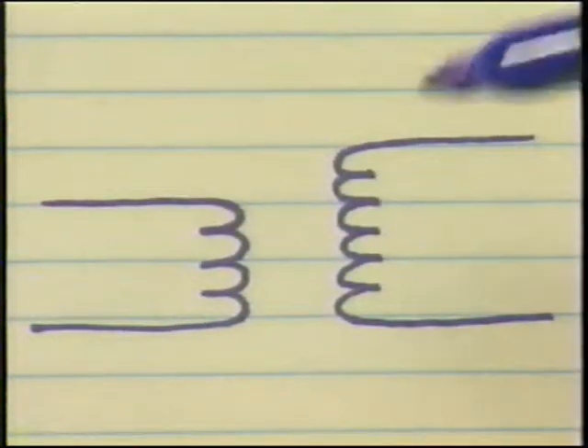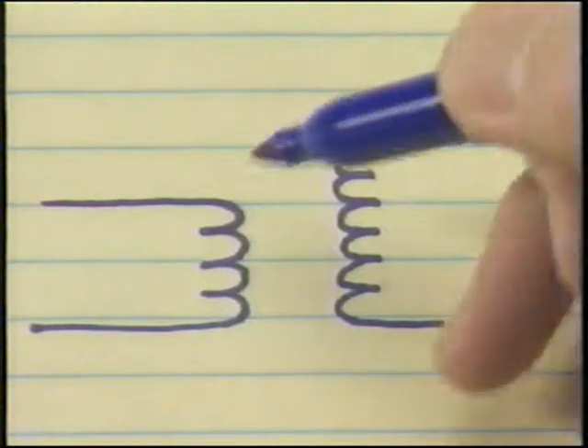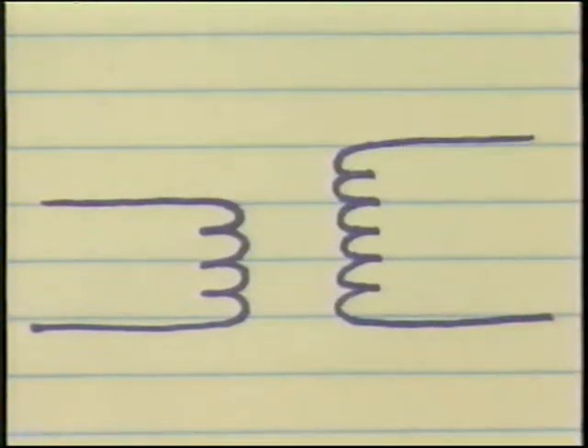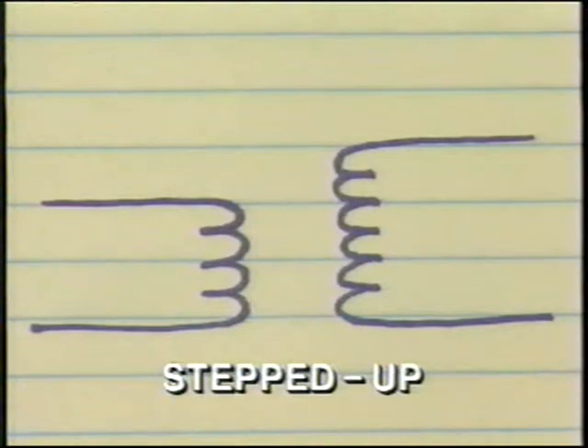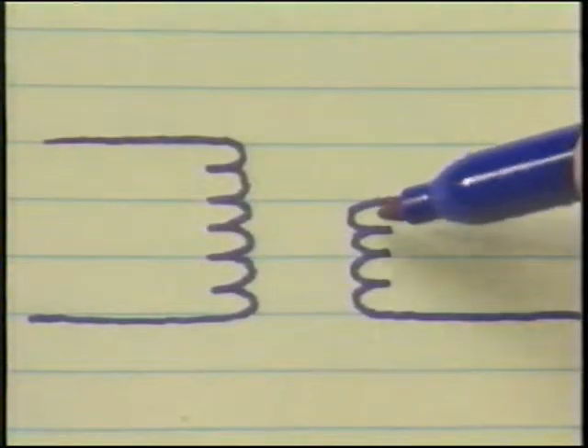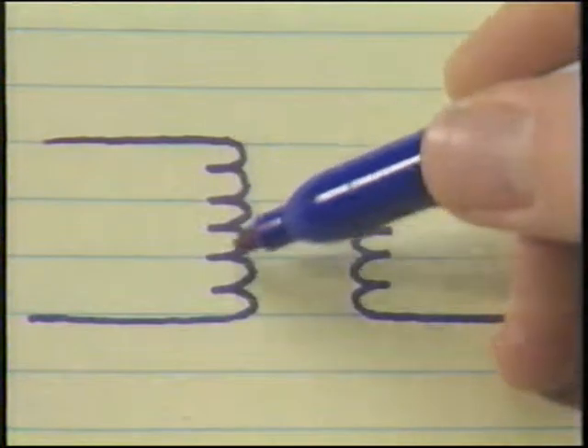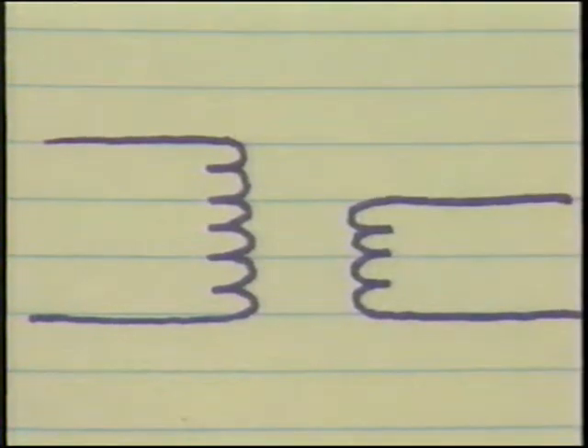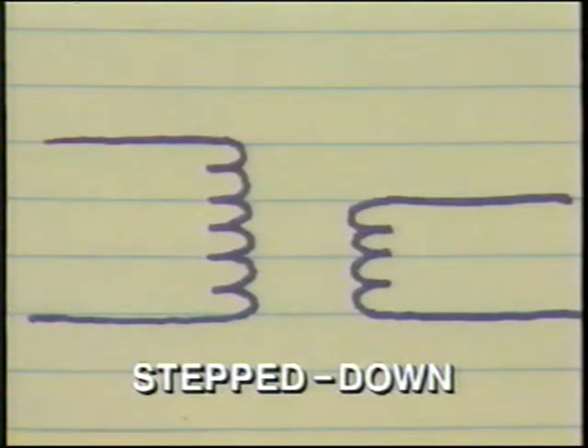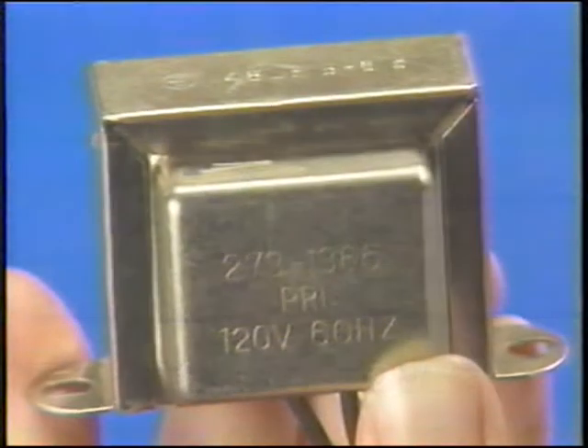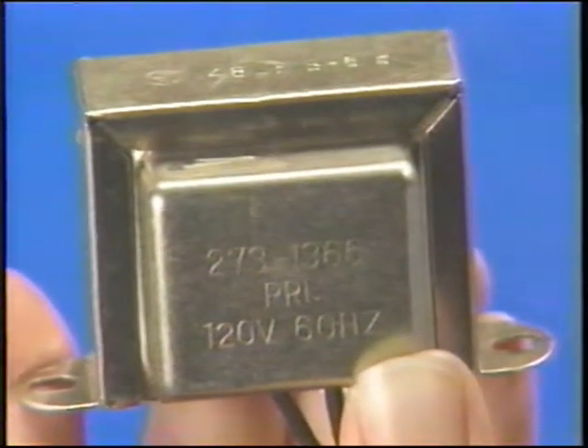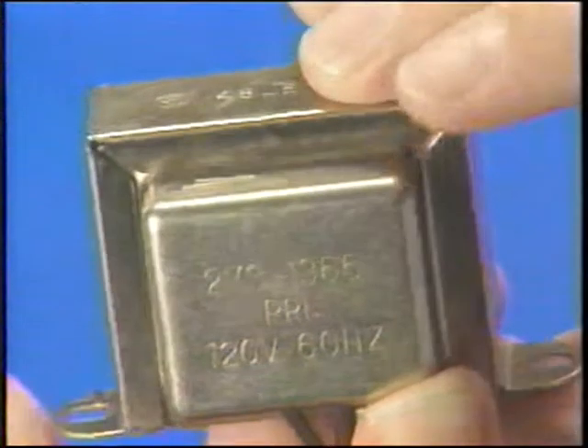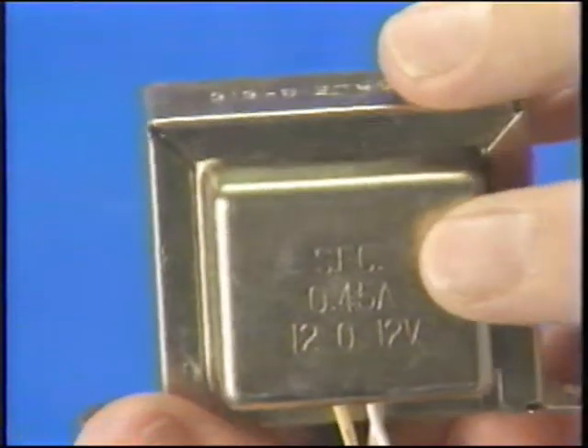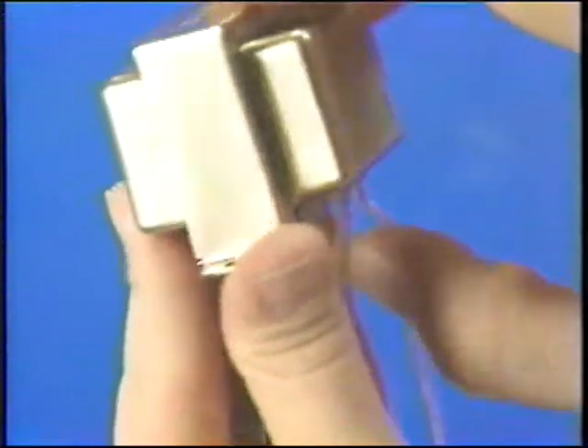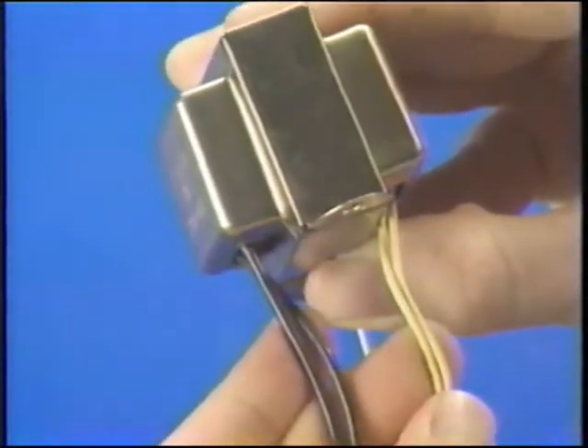From this example, you can see that if there are more turns in the secondary than the primary, then the secondary voltage will be greater or will be stepped up. On the other hand, if the number of turns in the secondary is less than that of the primary, then the voltage will be smaller or stepped down. Special care must be taken when wiring the transformer into a circuit. If the secondary and primary connections are reversed, severe damage may result. The primary and secondary connections are indicated by markings or by means of a color code. Be sure you know which is which.